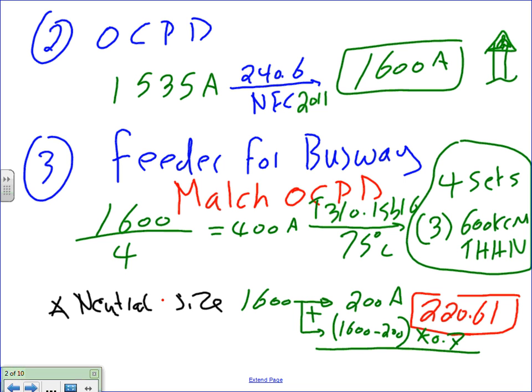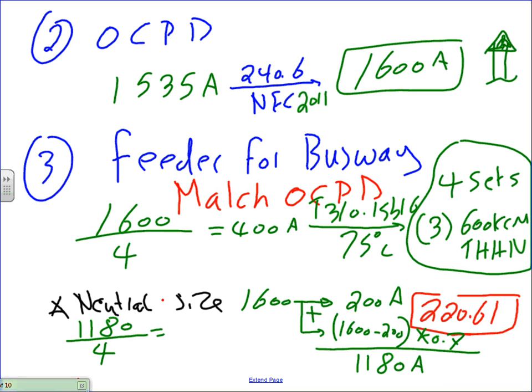When you end up with this, guys, you end up with 1180 amps. Okay? Then you do the sizing. So you basically reduce your neutral because the code allows you to cut anything by 70% higher than 200 amp. Okay? So the rest is piece of cake. Then I'm going to start with 1180. Now, Chris, since I'm already locked with four sets, I have to do four sets. I have no choice because the phases are four sets for the most part.